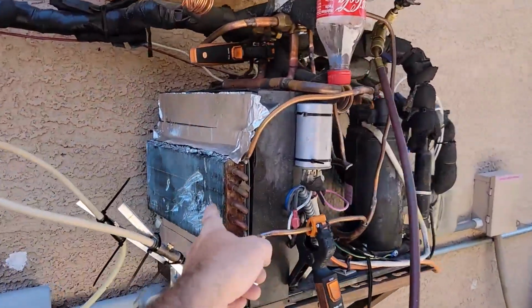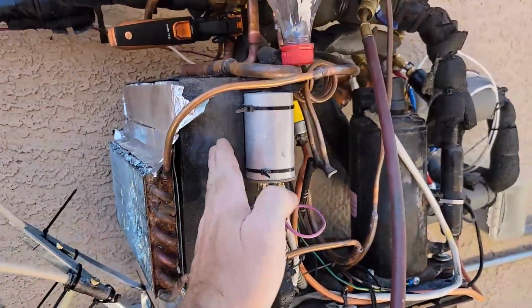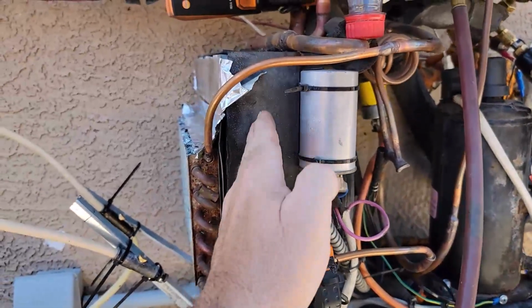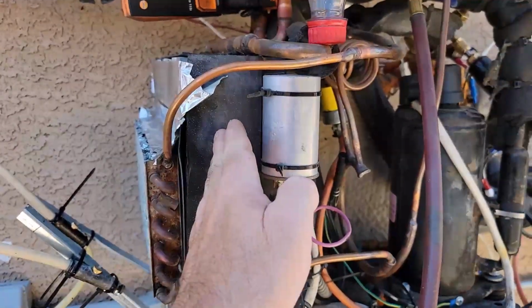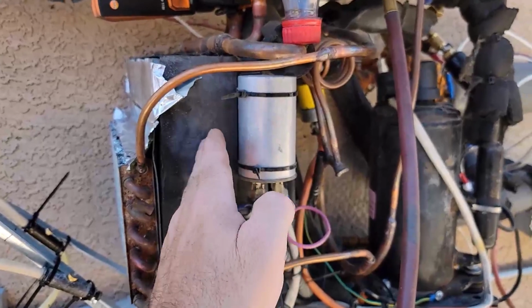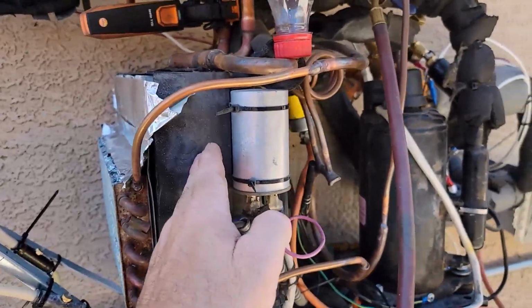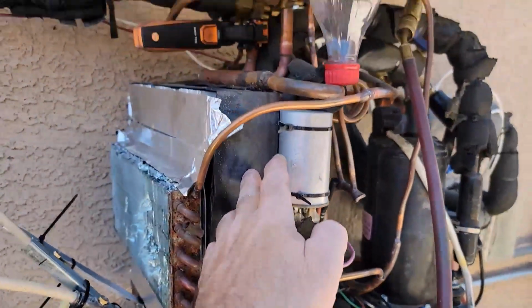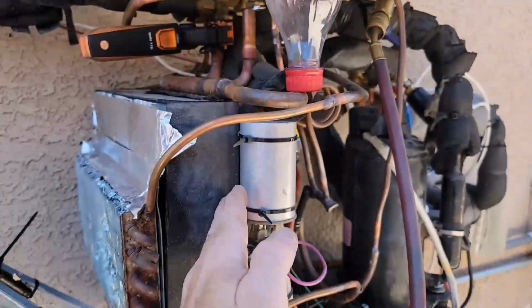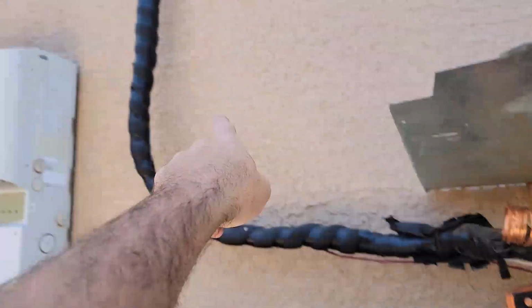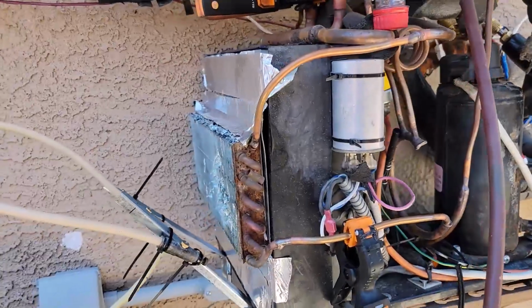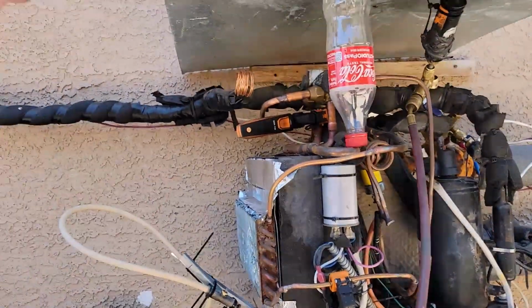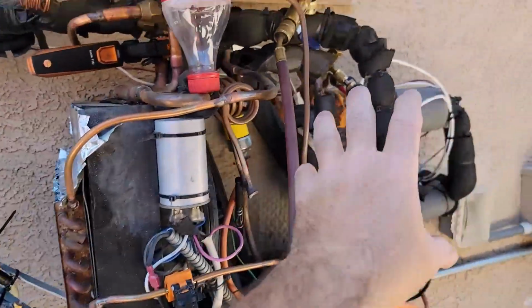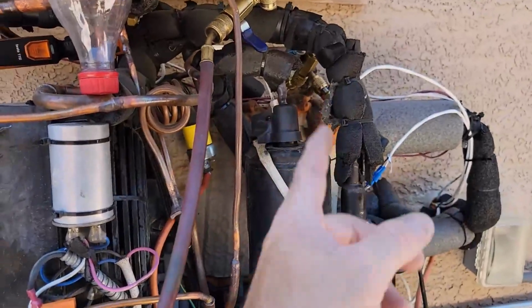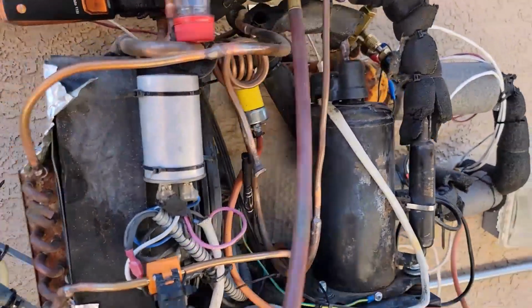I did this at the beginning of summer. This coil here is the outdoor coil for wintertime. It's just an evap coil, strictly with a capillary tube metering device, and I have some isolation valves. So that one's shut off during the summer, and instead it's using the indoor high wall to absorb heat and air condition that space, for the heat pump to add heat to my heat exchanger to the water tank.